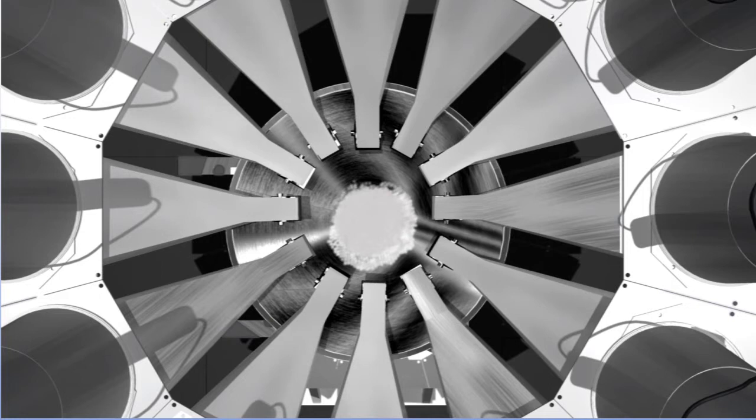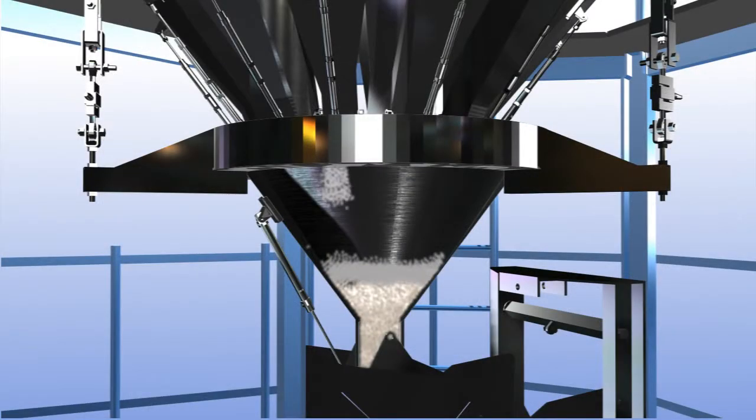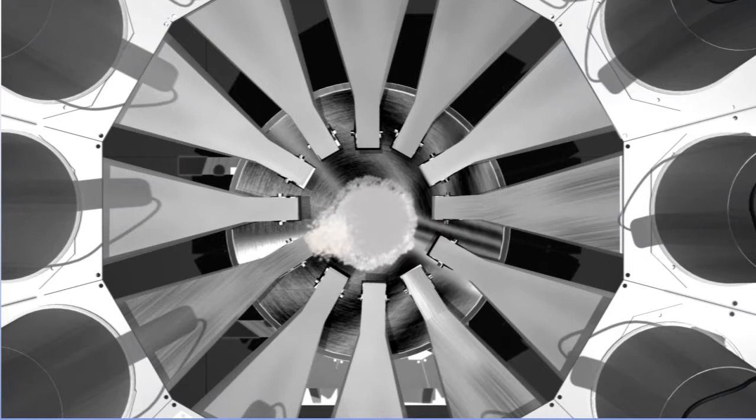Each ingredient is discharged in turn from its intermediate hopper. The ingredients are discharged into the weighing hopper which is equipped with three hanging load cells. PelletSave's controller predetermines the recipe ingredient combination for each of the factory's production machines. The relative quantity of each component is derived from this predefined recipe.